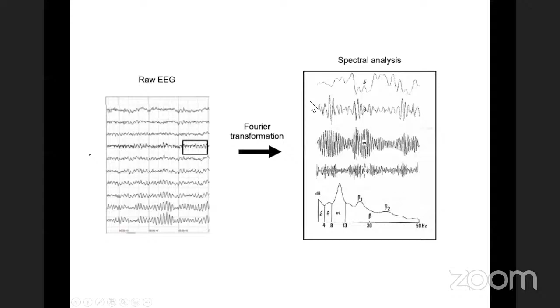The basic principle here is that the EEG activity is recorded from the electrodes placed on the forehead. Then from the raw EEG, the analog signal is amplified and converted into a digital domain. Various algorithms are applied to the frequency, amplitude, and latency, and a single number is generated, which is the dimensionless index, which is scaled between 0 to 100. And this number signifies the existing state of consciousness of the patient, with a value of 100 signifying an awake state and a value of 0 occurring at the isoelectric EEG.